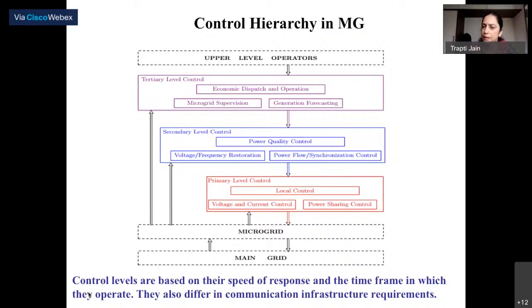Then comes the secondary level control, which we can call the energy management system. It operates in the range of, I think, 1 to 10 seconds, and handles voltage or frequency restoration, power quality control, and power flow or synchronization control. The third level is tertiary level control, which performs economic dispatch and operation, microgrid supervision, and generation forecasting. The time scale of operation of this tertiary level is several minutes. So these kinds of controls are present in the microgrid.